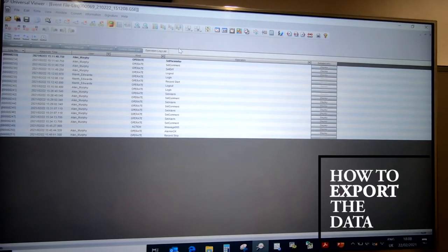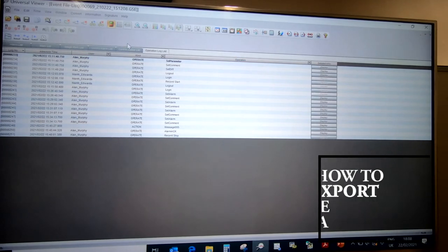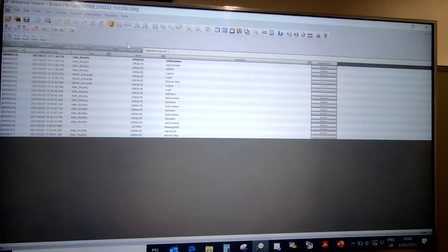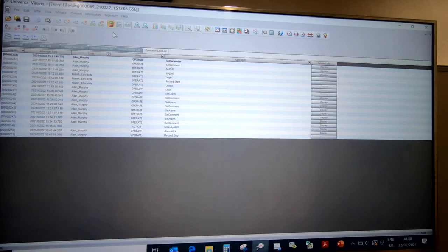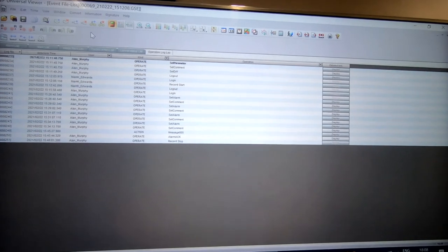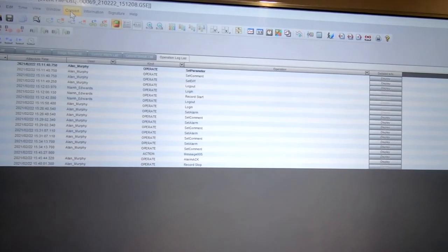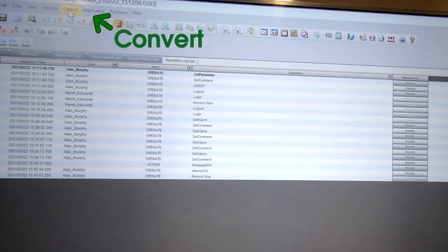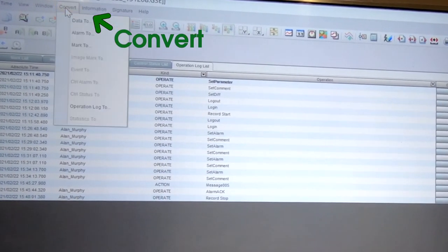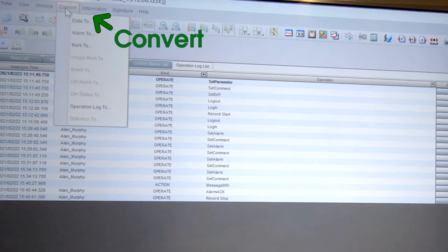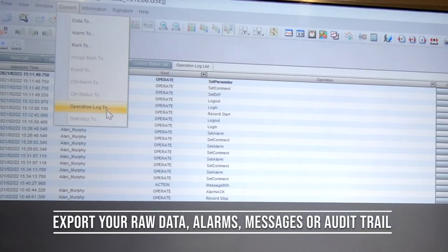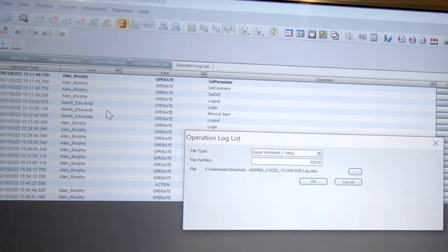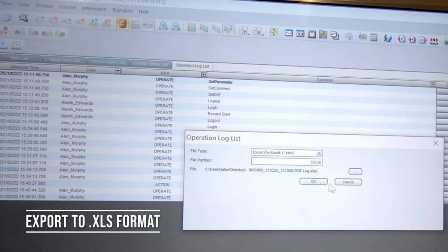If you choose to export the data for internal reasons, obviously if you export it to an editable format it kind of steps outside compliance, but a lot of customers do like to export the data for their own internal reporting reasons. You can simply click on convert and you can choose to export your alarms, your messages, or your operation log, select a location, and then export it to .xls format.